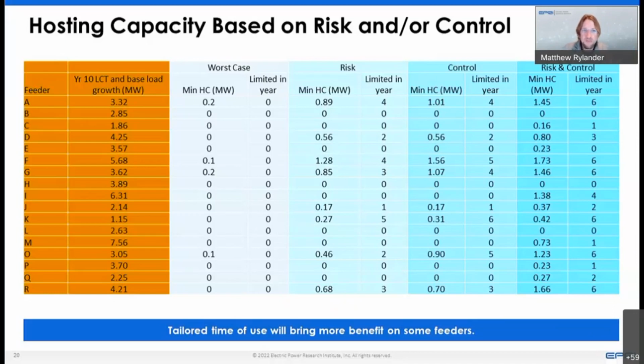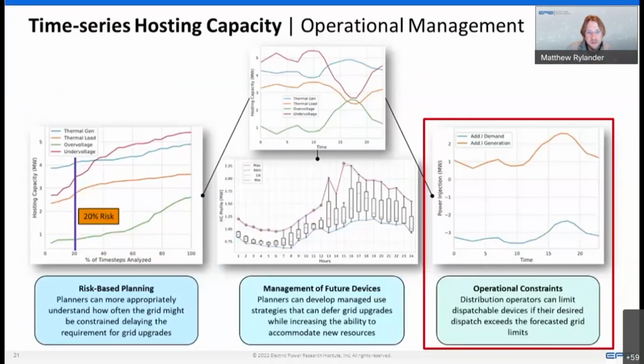So one of the big takeaways from this whole assessment was: look across the grid holistically and identify where we either need grid reinforcement or where we can get significant advantage from just a little control of the devices themselves. It's not just that these time-based hosting capacity curves give us risk-based planning—they also give insight into device management.